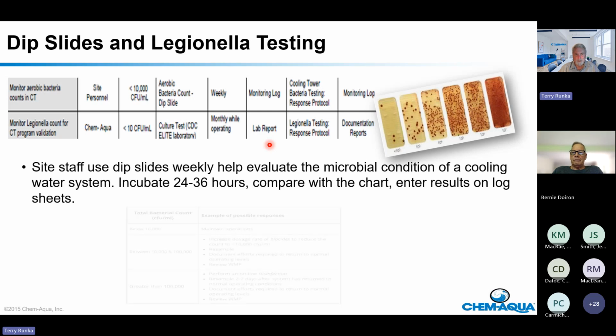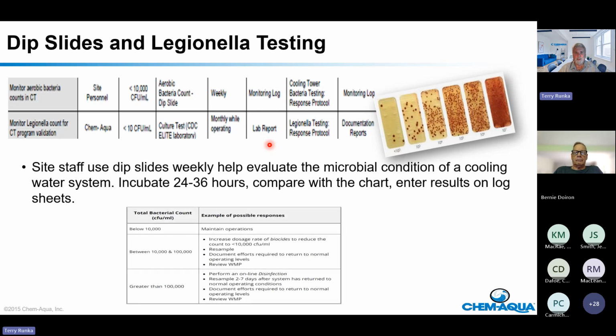Dip slides and Legionella testing - I should not put these two things in the title, because one has zero correlation to the other. Dip slides have no correlation to Legionella. You could have 1 billion colony forming units of total aerobic bacteria in your cooling tower and have no Legionella bacteria. You could have 10 colony forming units of total aerobic bacteria, and 10 of them are Legionella. However, it has been an industry standard forever that we do a dip slide, and some standards include it, some don't.